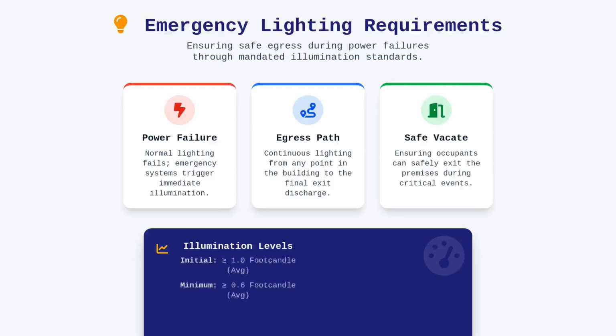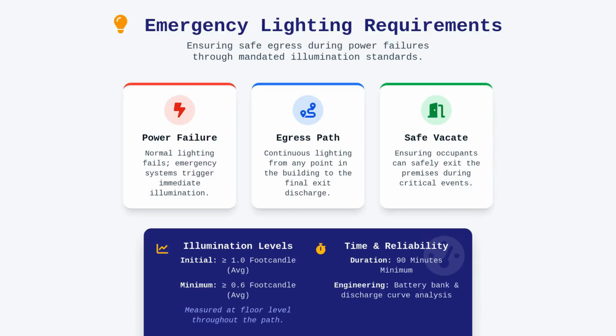The core requirement mandates an initial average illumination of at least 1 foot candle along the path of travel, measured at the floor level. It is crucial to remember that this intensity is permitted to decay over the required 90-minute duration, provided it does not drop below an average of 0.6 foot candles at any point. This gradual performance degradation is a critical design metric that engineers must account for when sizing battery banks and evaluating discharge curves to ensure that the illumination remains functional throughout the life of the event.